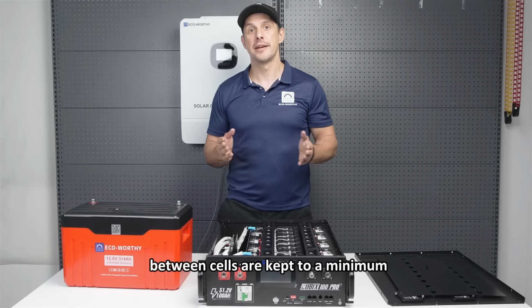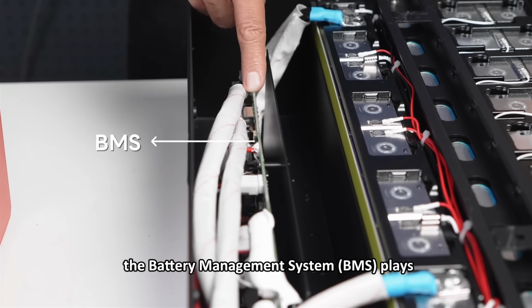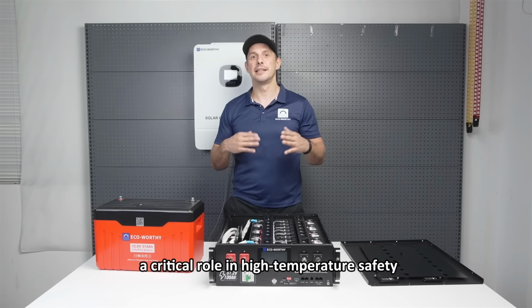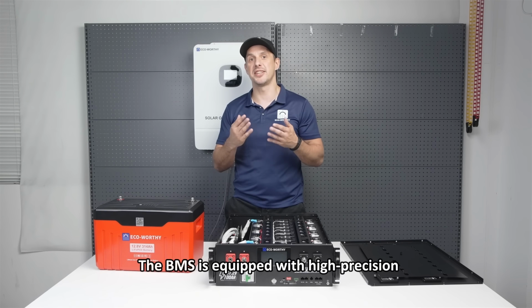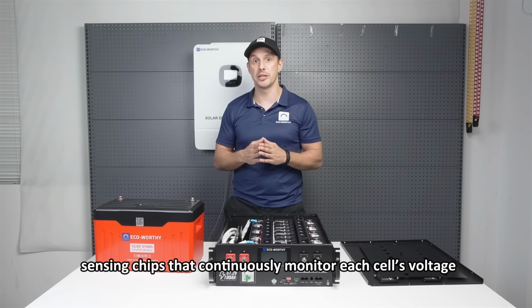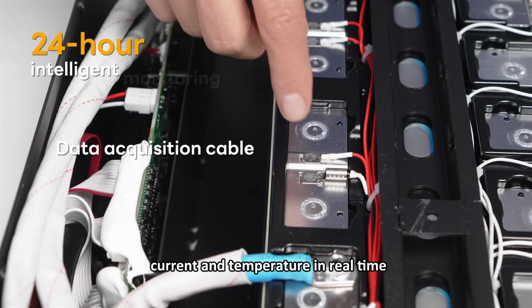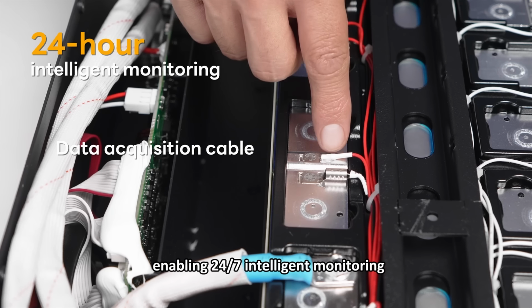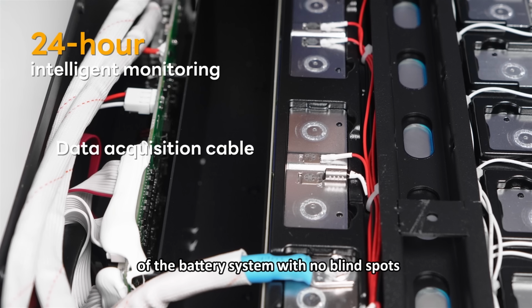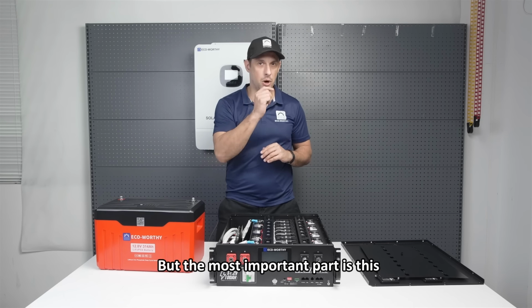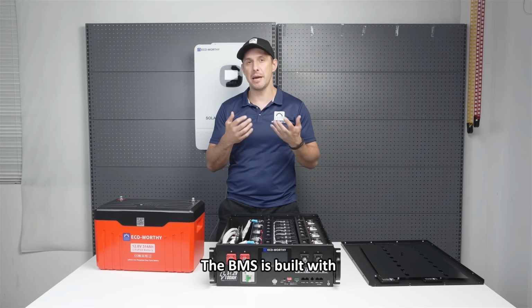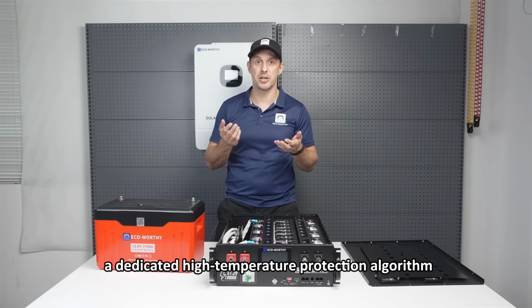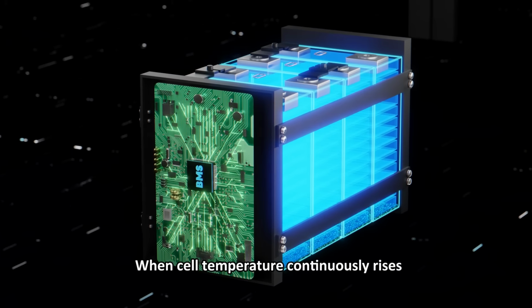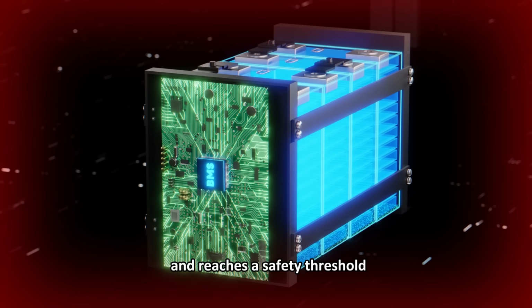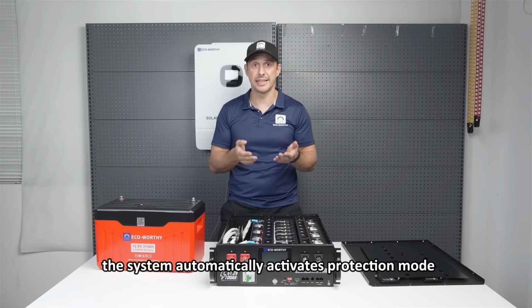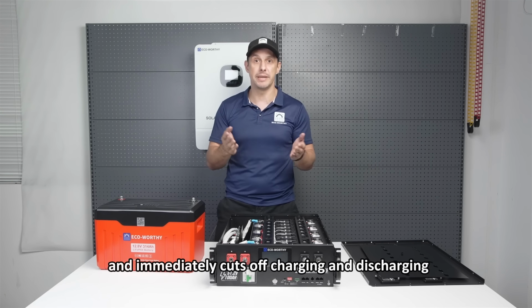Next, the battery management system plays a critical role in high temperature safety. The BMS is equipped with high precision sensing chips that continuously monitor each cell's voltage, current and temperature in real time, enabling 24/7 intelligent monitoring of the battery system with no blind spots. But the most important part is this: the BMS is built with a dedicated high temperature protection algorithm. When cell temperature continuously rises and reaches a safety threshold, the system automatically activates protection mode and immediately cuts off charging and discharging.